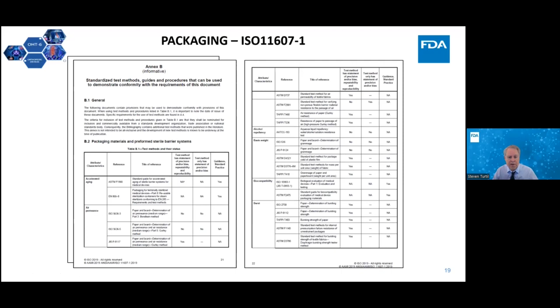Everything that appears here is not necessarily an FDA recognized standard. So again, you have to turn to our database just to make sure. What I'm going to do is focus in on the left page, and we're going to look a little closer just to give you an example of what's in here. Because we're going to be talking about accelerated aging now, this gives you an introduction to the annex, but also an introduction to each particular standard and some of the details and relevance of it. So this is accelerated aging, ASTM F1980.